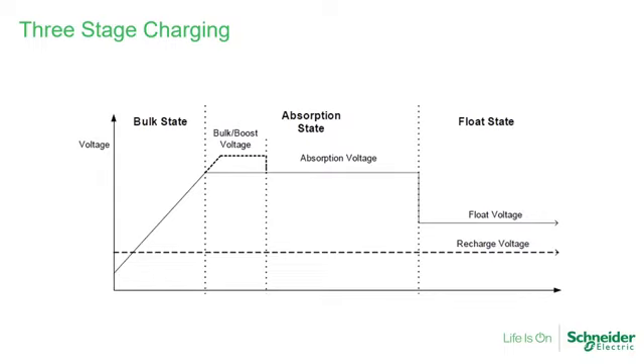So traditionally, we say that for a lead acid battery, once we've reached the bulk voltage, we are about 80, 90% state of charge. We need the next stage, which is the absorption stage, to complete the charge. Once we reach the end of the absorption stage, then a lead acid battery should be fully charged. The next stage, sometimes also called trickle charging or float, is just to simply maintain those batteries. So this is a very typical profile of what will happen in a day for a lead acid battery.